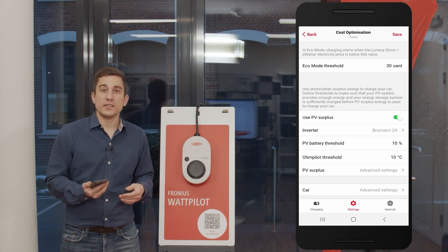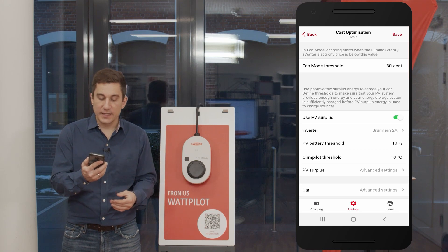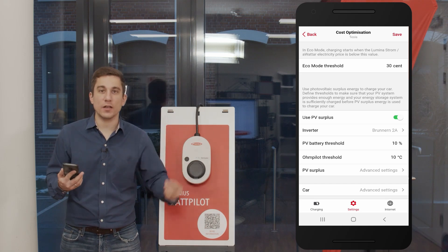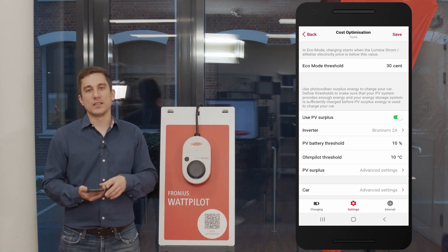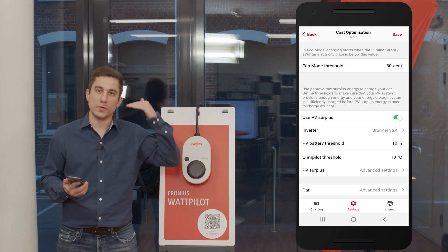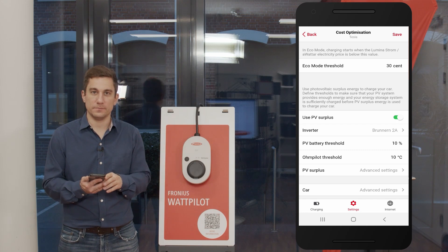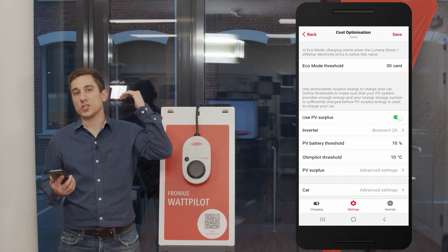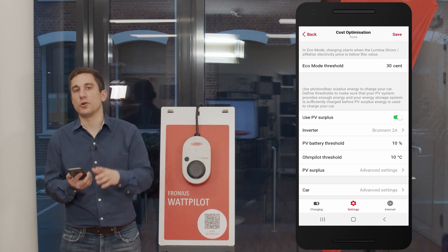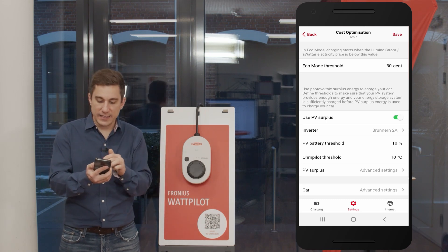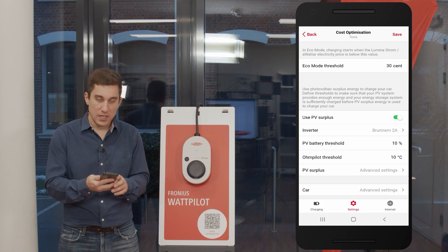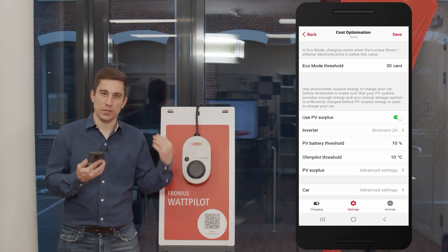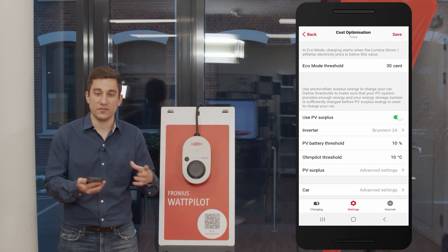Important note: the prioritization between the Ohmpilot and the stationary PV battery system must also be set separately in the web interface of the Fronius inverter, under the energy management functionality. There you can set, for example, PV battery storage as priority number one and Ohmpilot as priority number two. These two systems — the Fronius Wattpilot app settings and the inverter web interface settings — always work together.